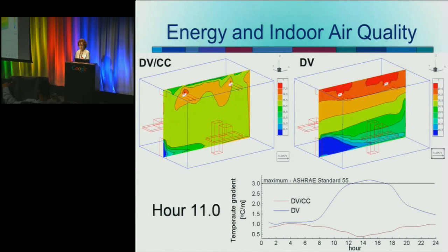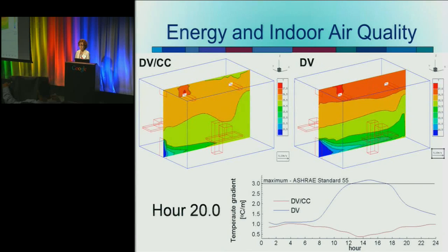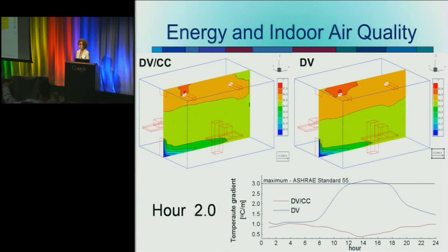And we can find, here is a temperature distribution. Blue is 20 degrees Celsius or 70 Fahrenheit. And 27 is red, which is close to the ceiling. I was not worried about the temperatures at the ceiling because nobody is up there in this particular setup.